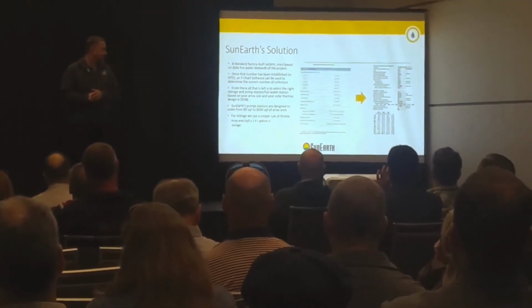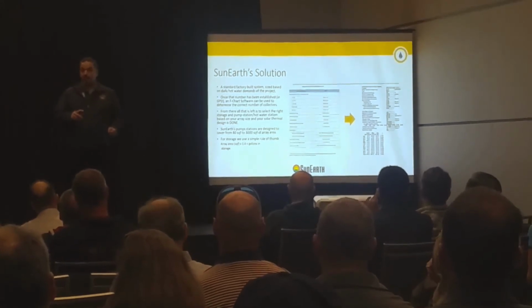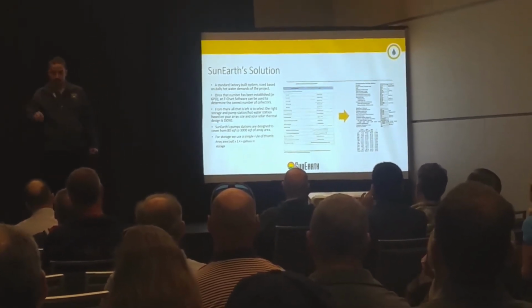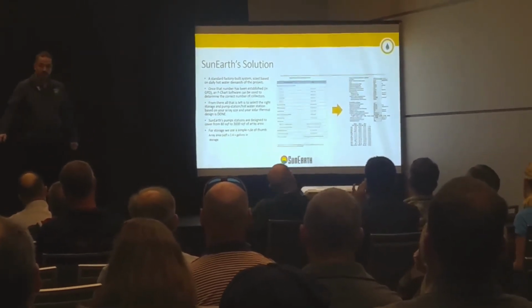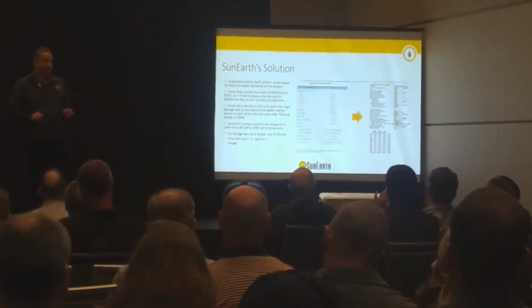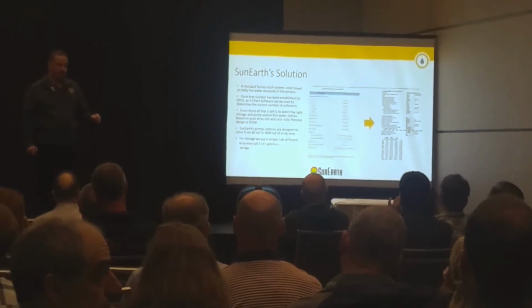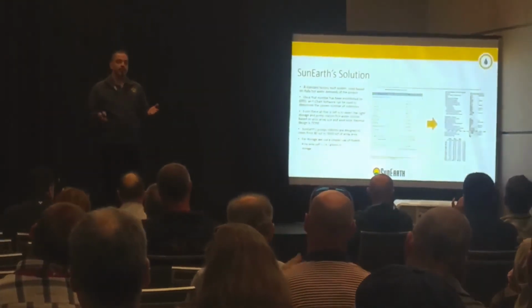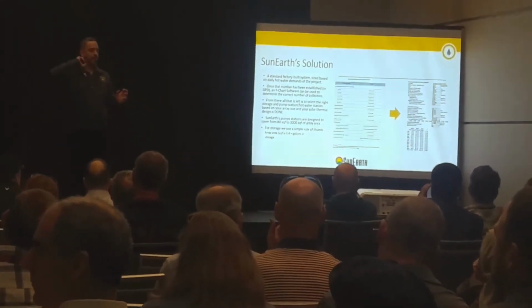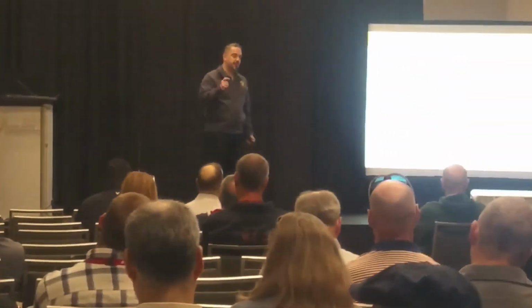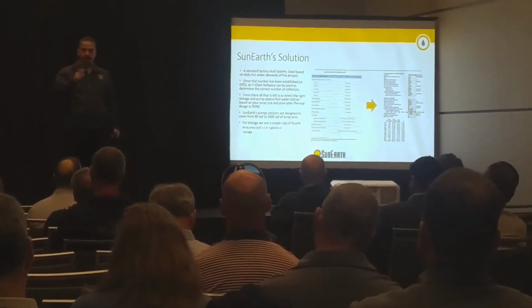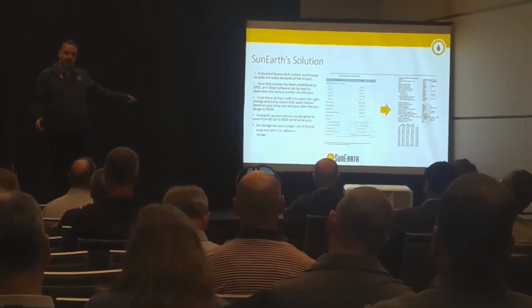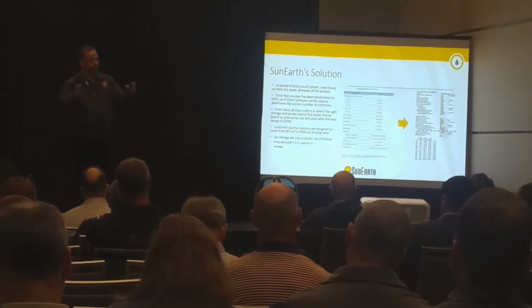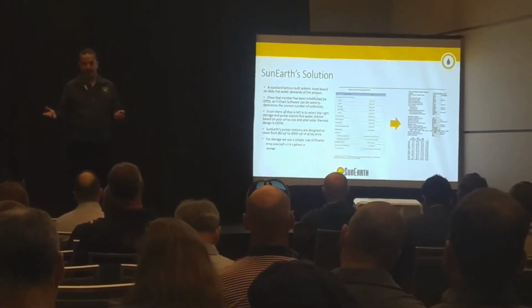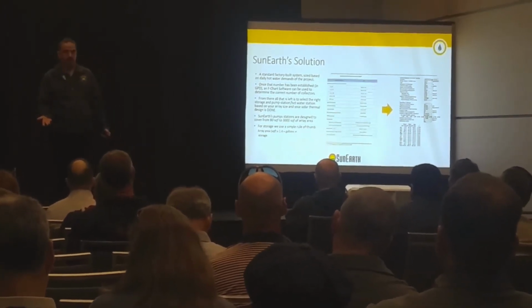For example, for an apartment building, if you have 2 to 20 units, we'll tell you to use 42 gallons per day per unit to establish how much hot water you will need. Once we have that number in gallons, we then convert that information to the number of collectors that you will need using an F-chart. And now SunEarth has the product. Once you establish how big of an array you need for your collector, the rest is very easy for us, because we already have the right pump station solution to go with the specific size of array that you're using on your project. And from there, you establish the size of storage that you would need. The general rule of thumb for storage calculation is we calculate the size of the array. For a commercial system, we multiply that by a 1.4 factor, and that will give you the size of storage that you would need in gallons.